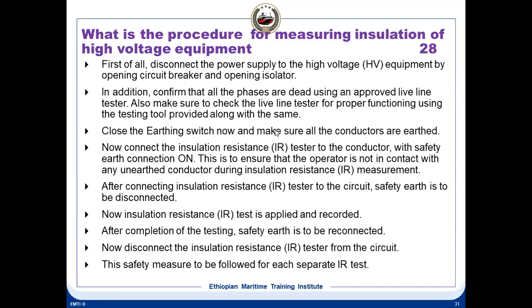So close the earthing switch now and make sure the conductors are earthed. And now connect the insulation resistance tester to the conductor. Then you connect the Megger to the conductor with a safety earth connection on. This is to ensure that the operator is not in contact with any unearthed conductor during the insulation resistance test. So after you connect the insulation resistance tester, the safety earth is to be removed. Remove the earth connection, otherwise you cannot measure it because all the 3 phases are now grounded. You have connected the insulation tester, you remove the ground, then you measure it. Now insulation resistance is applied and recorded.